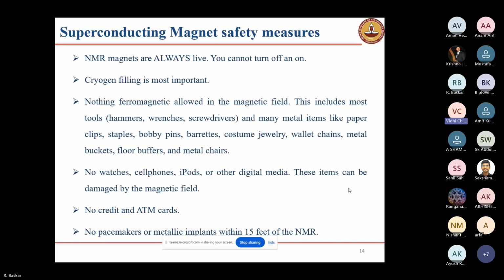Go ahead. So these are the safety measures we have to follow for NMR magnets. NMR magnets are always live. We cannot switch them on and we cannot switch them off. Once energized, that's all. Once quenched, re-energizing it costs a lot. So we have to maintain the helium and liquid nitrogen level. That cryogen filling is most important. If we fail, the magnet will quench, and we are in trouble.